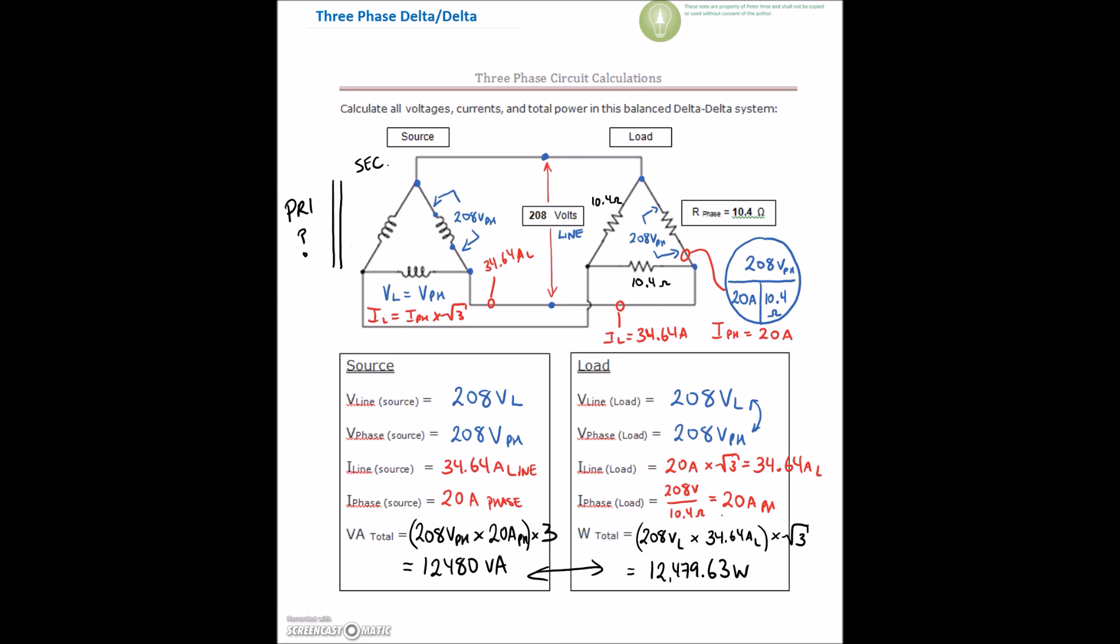Let's just walk through one more time what we did. We took the 208 volts on the line. We found that it was identical voltage on the phase. We took that 208 divided by the 10.4, and we found 20 amps on the phase. There's 20 amps here, and there's 20 amps here, but they're not happening at the same time.